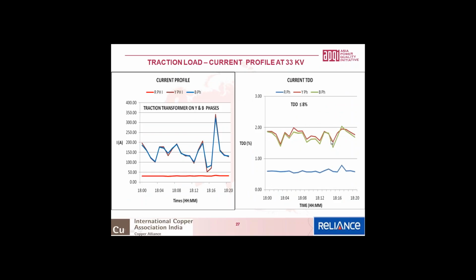We are showing TDD, total demand distortion. As per IEEE, for a voltage level of 33 kV and this fault level, it should be less than 8%, but the actual TDD observed for this traction load is less than 2%. Therefore, as you go to higher and higher voltage levels, the amount of harmonic content the system can absorb is also higher because of the very high fault levels.